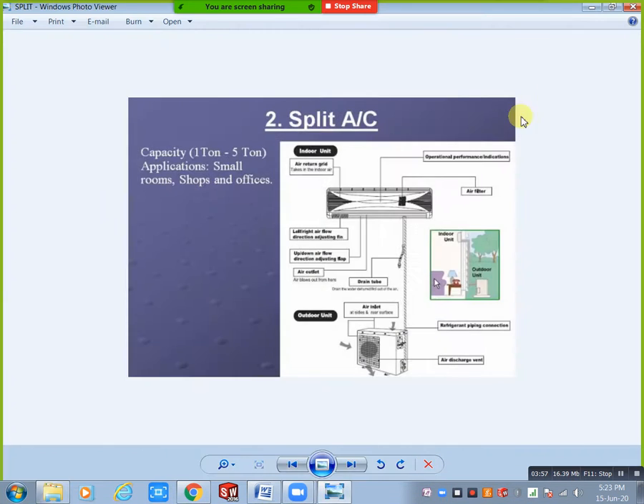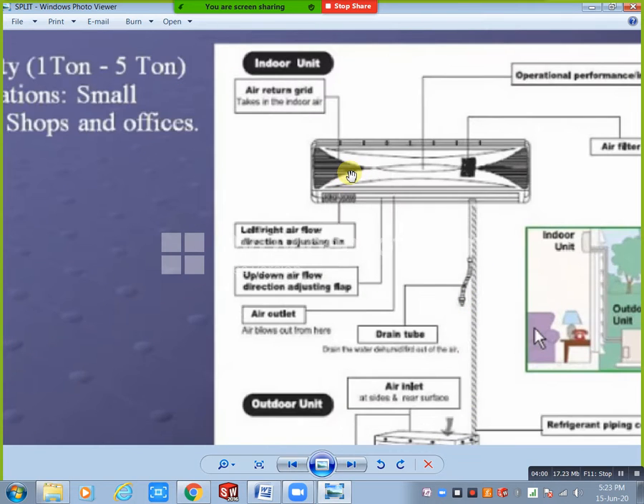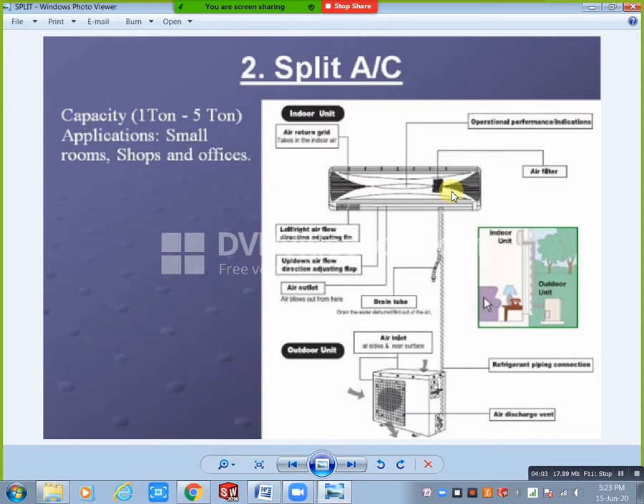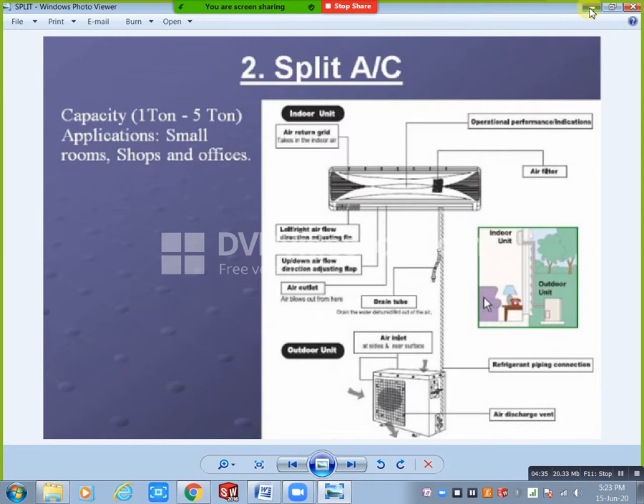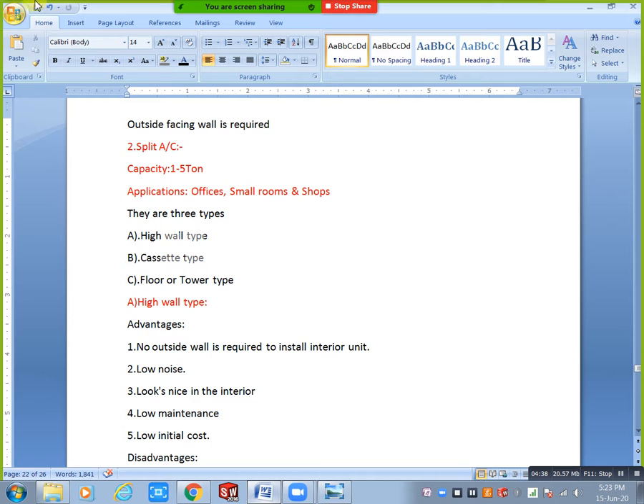Looking at this picture: here we have the indoor unit and outdoor unit. Copper pipes run at the back side. The drain pipe runs below the copper pipes always, and that drain pipe is connected to the floor drain. For the floor drain connection, we use a U-trap.